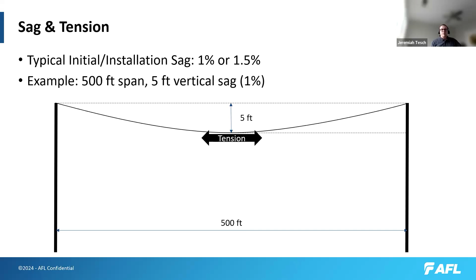All right, and then as I mentioned, there are some electrical considerations if you're on a higher voltage transmission line. So you have some risk to the cable from dry band arcing or tracking, and then corona. So we have solutions for that, and AFL performs an analysis for customers, and I'm sure other manufacturers have different ways of handling this as well. But we perform an analysis on the structure based on relative position, voltage, and things like that.